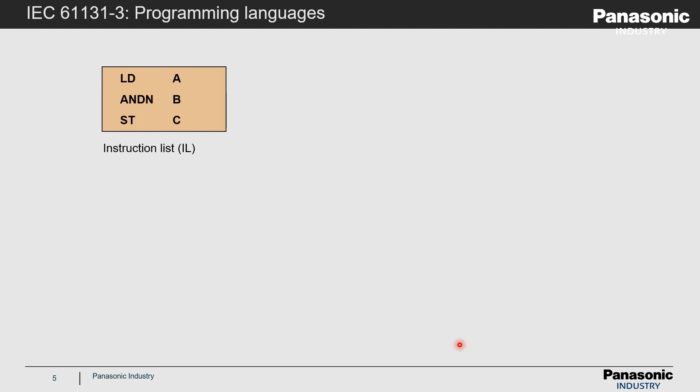Part 3 of the IEC standard also defines five different programming languages from which the user can select. On the upper left of the slide, the instruction list is shown. It is a textual language which is, however, already deprecated in the third edition of the IEC standard, so it is not recommended to use it anymore.